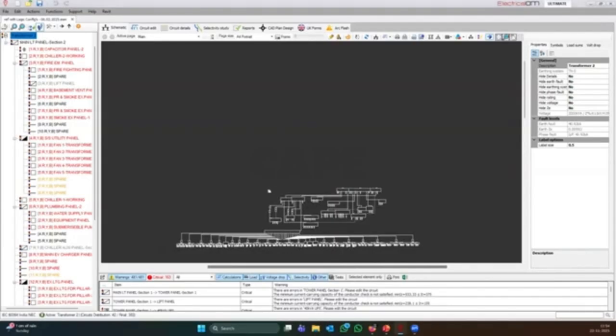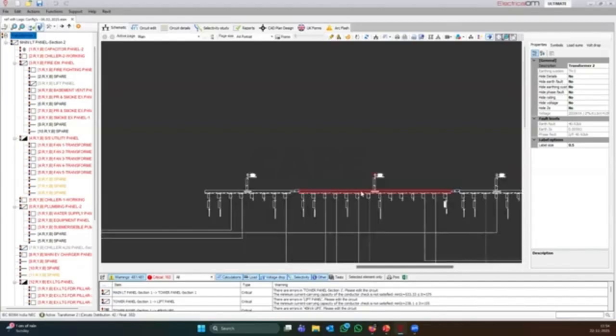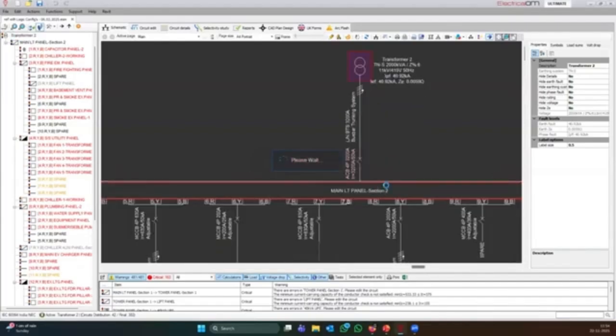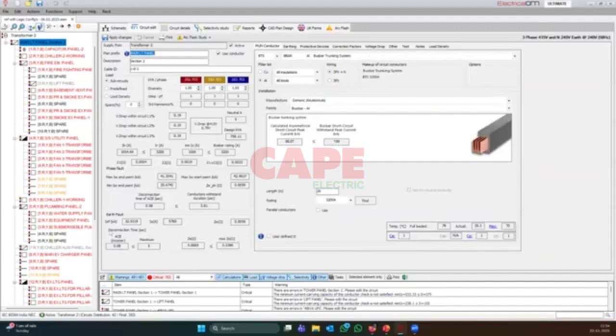Now, when you take this circuit as an example, at this area, the loop impedance is going to be something around this. It will also show you all the loop impedance, and what the maximum Z percentage is. It will automatically calculate the resistance and reactance. I have put in a busbar trunking system, and it will automatically show these issues.